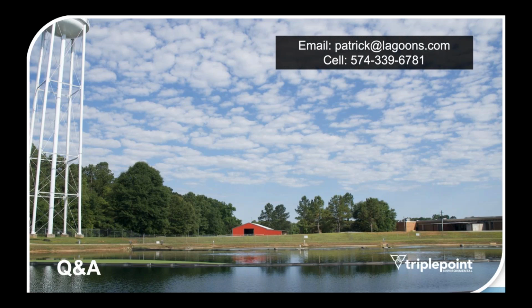And again, this goes back to that slide where I was talking about circular logic. It's sort of confusing, but at the end of the day, because all lagoons are set up with a certain hydraulic volume, even if you're recirculating within the lagoon, what comes in must go out, and it's going to be equal. You're not increasing your daily flow by recirculating. Your daily flow stays the same. You're just moving that water around the system more frequently.